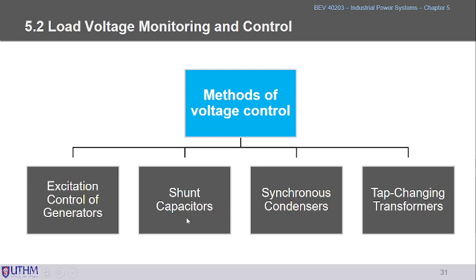And or we can use the shunt capacitor. A shunt capacitor is very famous because this is the capacitor bank, or power factor corrector. This is at the load level, so normally we install it at the load level. Same with the synchronous condenser, it is normally installed at the load level also, because we can optimize the voltage due to the load changes at the load bus there. The synchronous condenser is an overexcited synchronous machine, or synchronous motor.